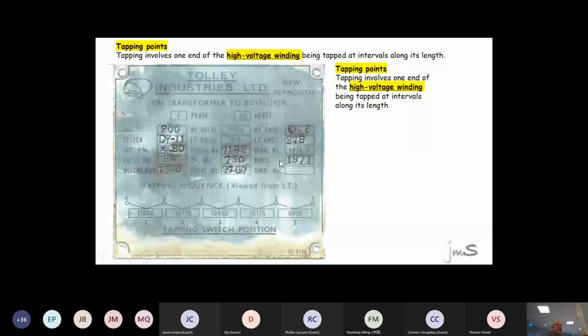Right, now we see a transformer nameplate. You will all be able to see it. Can you all see it? Right, can you all see that this transformer has got tappings? What's the purpose of a tapping? A, is it there to let the transformer look nice? Or do you think it's there so that you can change the voltage? So if it's 11,000 volts, I can make it 10,000 volts or 11,900. I can set it up or down.